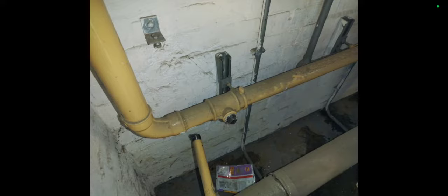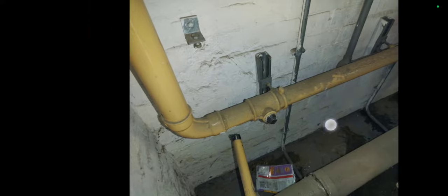I had to isolate the boiler on the left in the end because it was leaking, and I was doing a lot of extensive work on it. I just decided to cap it off because the heat exchanger was leaking. And then I put a note on it. I made it quite clear that this boiler is not to be used. Make it quite clear to people that the boiler is out of action. Do not leave any doubt in anyone's mind whether it's supposed to be on or off.